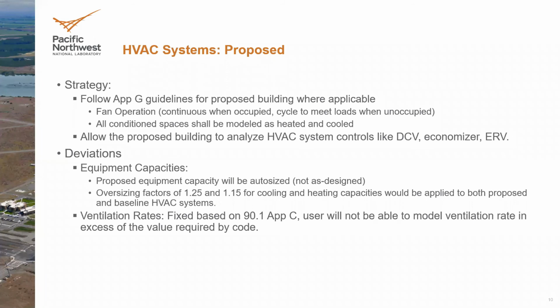Right, I mean I guess if you have thermodynamically a hydronic chilled beam - 4-pipe hydronic chilled beam with heating and cooling - it's not really any different than a DOAS feeding a fan coil or another DX unit that's providing local heating and cooling. You're still delivering conditioned outside air to a space and then further tempering it, whether that's adding heat or in some cases adding more cooling. It's just the mechanism of how that heat is provided, whether hydronic, electric, DX, etc.